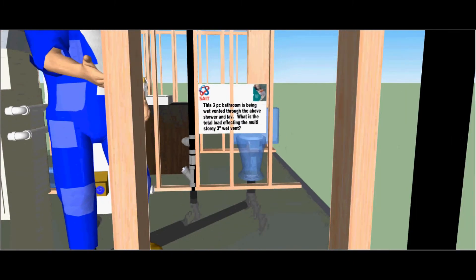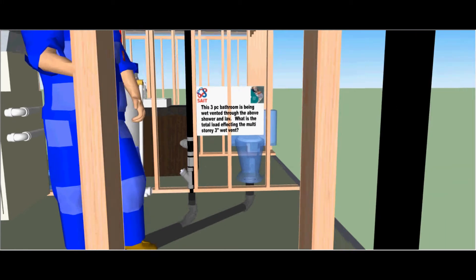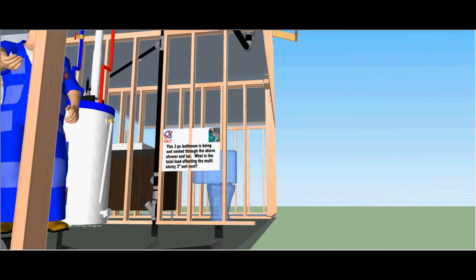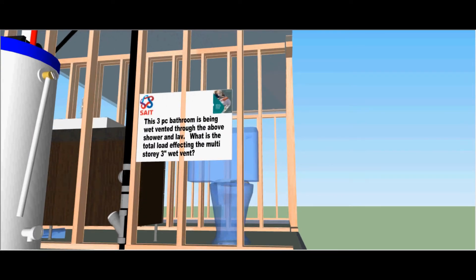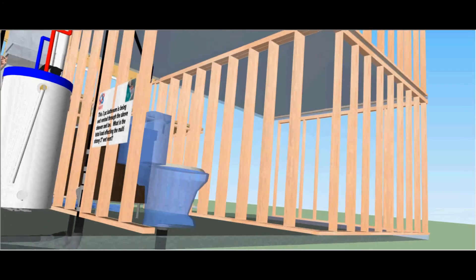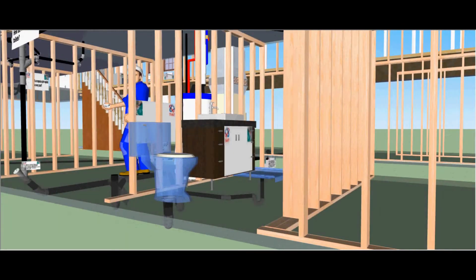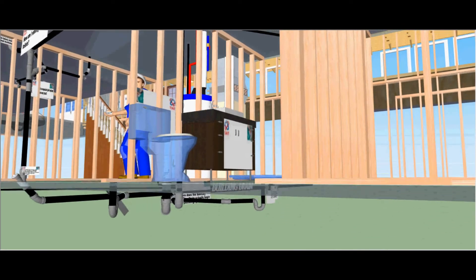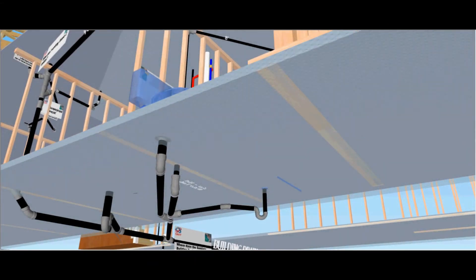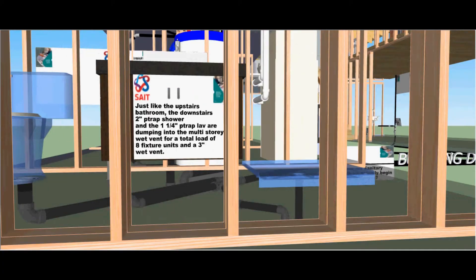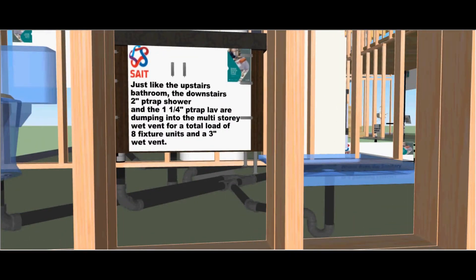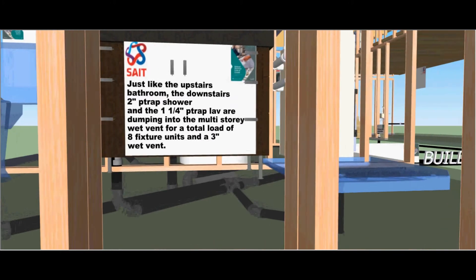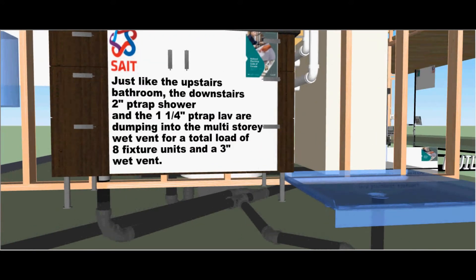Now we are going to run down to the 3 piece bathroom that is being wet vented through the shower and lav above. What is the total load affecting the full multi-storey wet vent? So in other words, this 3 piece bathroom is being wet vented through the shower and the lav above. As you can see here, we have a horizontal wet vent in the basement with the toilet being the last connection, a 2 inch shower and an inch and a quarter lav. Just like the upstairs bathroom, the downstairs 2 inch P-trap shower and the inch and a quarter P-trap lav are dumping into the multi-storey wet vent for a total load of 8 fixture units and a 3 inch wet vent.